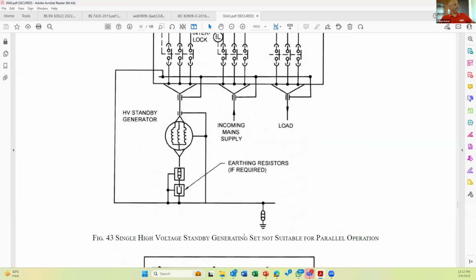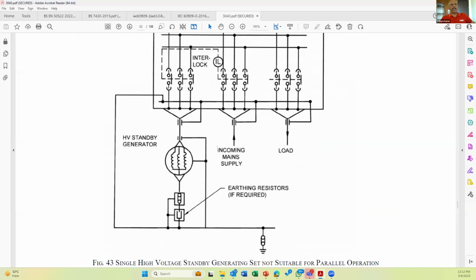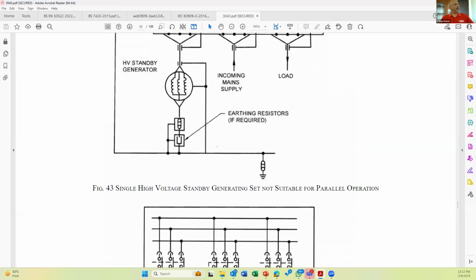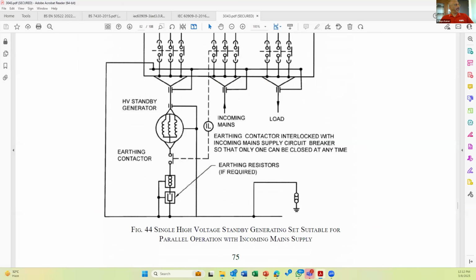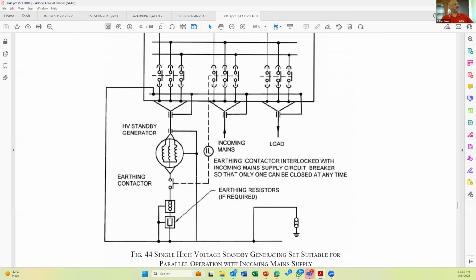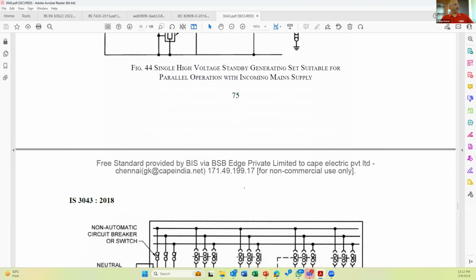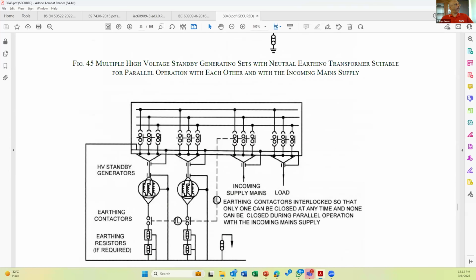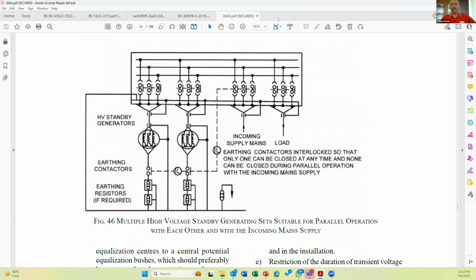The single high voltage standby generating set not suitable for parallel operation. That means the HT generator and the supply with the manual changeover. The next picture, single high voltage standby generator set suitable for parallel operation with incoming main supply. That means the main supply and the generator are synchronized, with NGR or without NGR. So you can find this information from these figures, figure number 43, 44, 45, also 46. So I recommend you please go through these figures and get the answer, please.